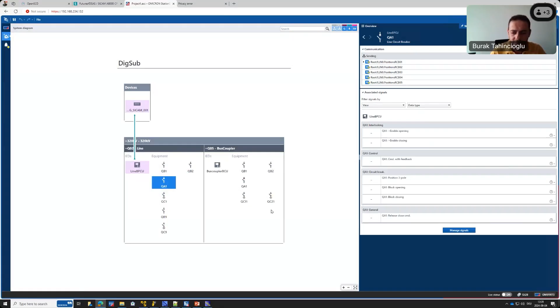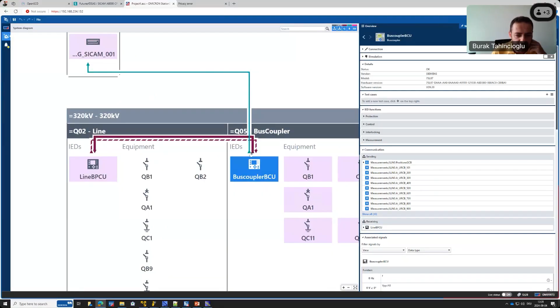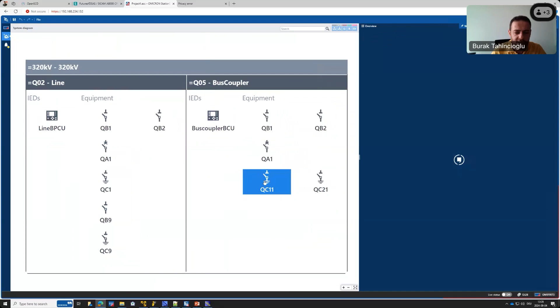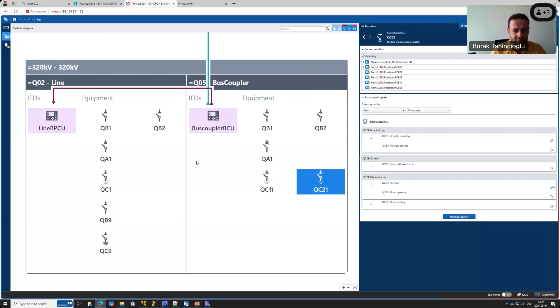Good. Now we can simulate this bus coupler IED because it's sending out some information of the switchgear to the line BCU. And I'll tell you the interlocking logic. If this busbar grounding switch or this busbar grounding switch is closed, then you would not be able to close this busbar disconnector. I would like to test this first. And also the other way around, if this is closed, this cannot be closed. That was the simpler interlocking logic that I want to test without having a physical IED with me.